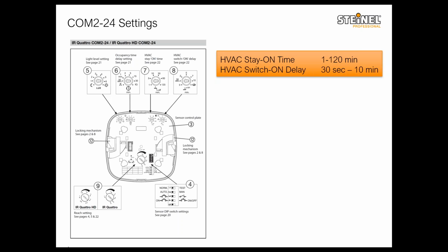One thing to keep in mind about COM2 sensors and the relay output is that it's auto on. As soon as you have occupancy, either the switch on delay will start counting, or if the switch on delay is set to 0, the relay will close and switch position and will give the signal to the HVAC, or if you're using it for receptacle control, to your contactor or power pack, so your second power pack. So there is no manual on setting. This output can't be used directly, at least for situations where you have a second light circuit that needs to be manual on, because this one only works as an auto on feature.